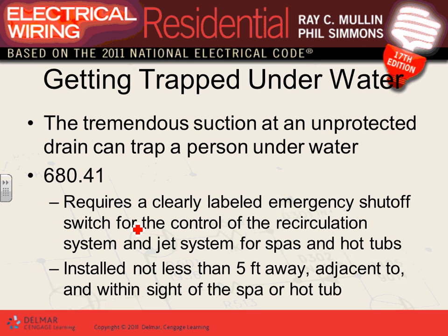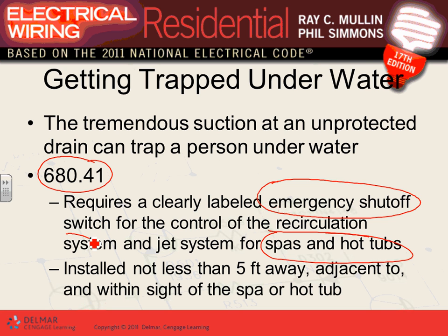So you guys heard about people being trapped underwater at the drain. I think in Minnesota, a young lady died. She got sucked into that trap, the drain. Because of all of this, the code requires an emergency shut-off. You have to have an emergency shut-off switch to control the recirculating system for the spas and the hot tubs. So you have a red mushroom push button. If you see somebody, a kid, being sucked through the circulating pump, I mean, some of these pumps have a lot of power. So you hit that mushroom head button, it shuts the circulation system and saves somebody from having their organs taken out of their belly.